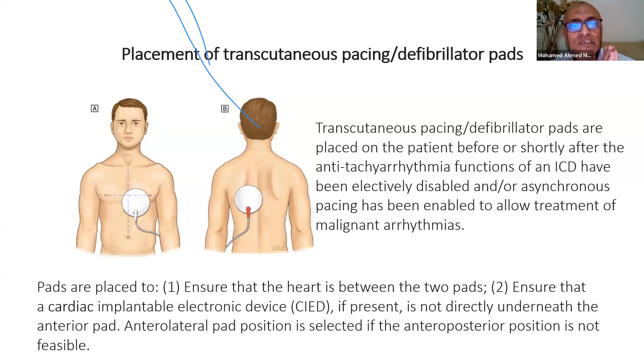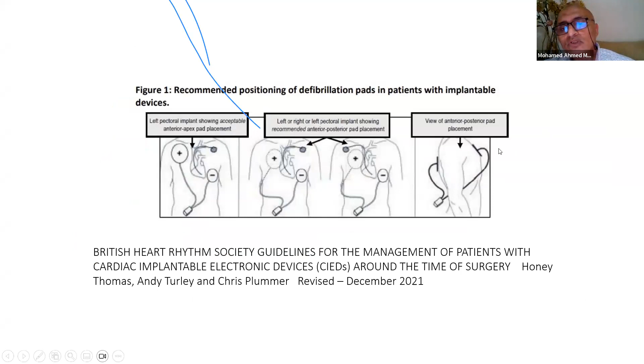Now we can remove the defibrillation pacing pads from the chest wall of the patient, and we can send the patient now to the ward. Before this, we have to keep the patient monitored either in the ICU or in the recovery, and we have to keep the pacing defibrillation pads attached to the chest wall of the patient. The precaution during attachment of these pads is we have to avoid putting the defibrillation pads on the device. So we can put them in anterolateral position like that, or in anteroposterior position away from the device.